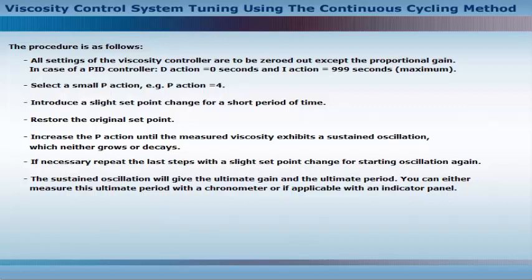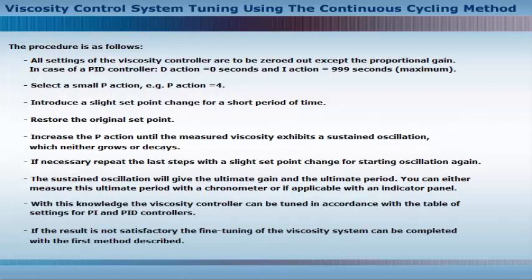The sustained oscillation will give the ultimate gain and the ultimate period. You can either measure this ultimate period with a chronometer or, if applicable, with an indicator panel. With this knowledge, the viscosity controller can be tuned in accordance with the table of settings for PI and PID controllers. If the result is not satisfactory, the fine-tuning of the viscosity system can be completed with the first method described.